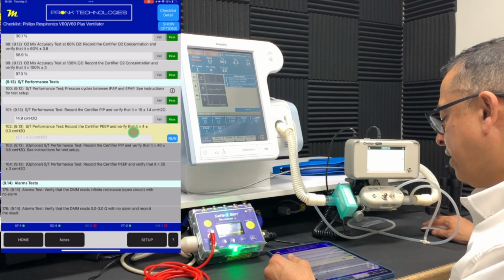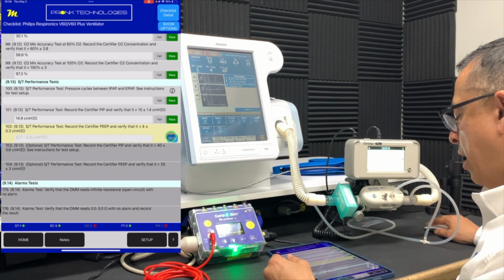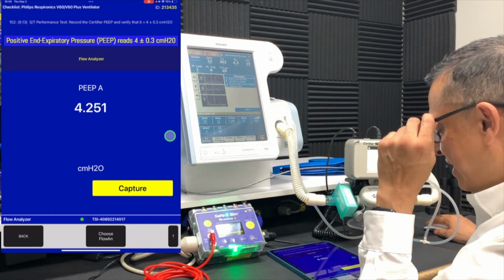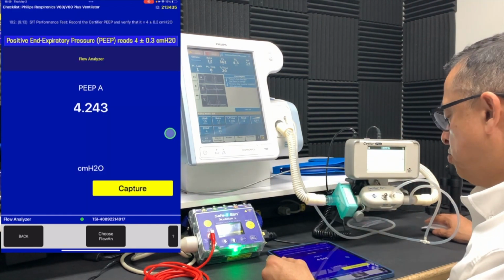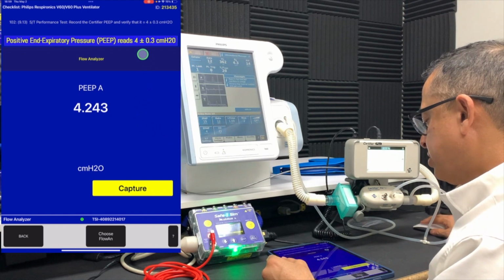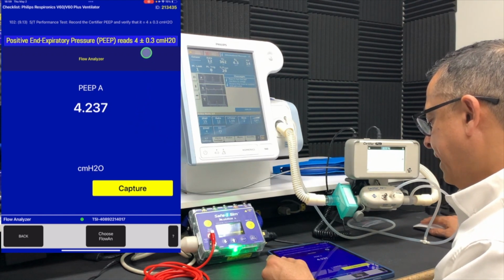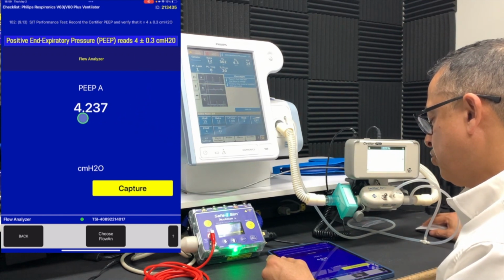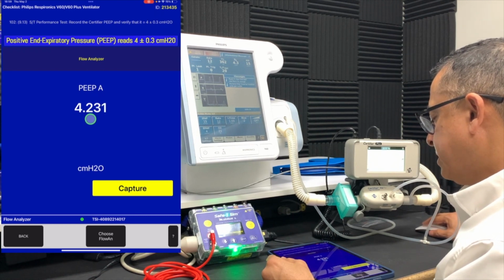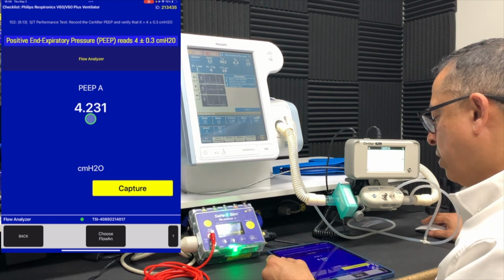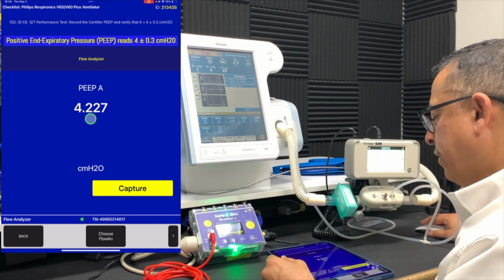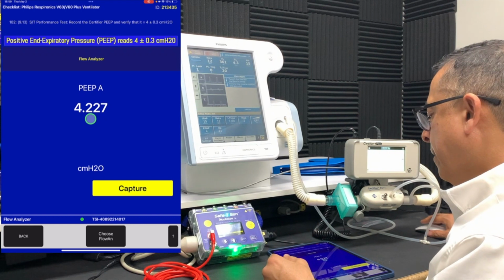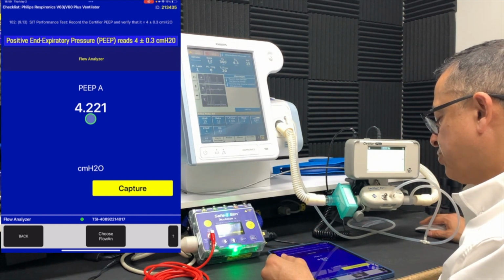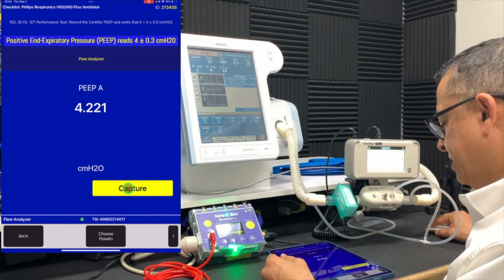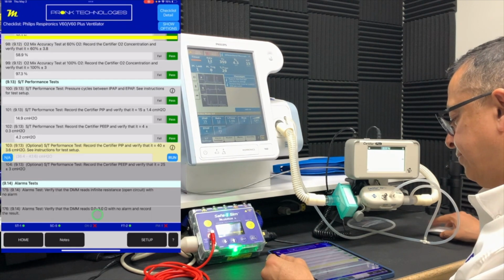And at the same time, we want to verify our PEEP. Our PEEP value is within the right tolerance. It should be within 4 plus or minus 0.3. And you can see here we're at 4.2. That is within tolerance. We'll monitor it a little bit longer, see if it stays stable. We'll want to make sure that positive end expiratory pressure stays within that limit. And it looks like it is. We'll go ahead and capture that value.